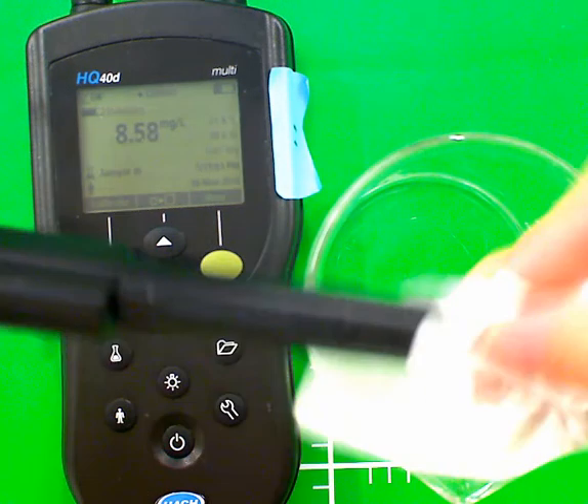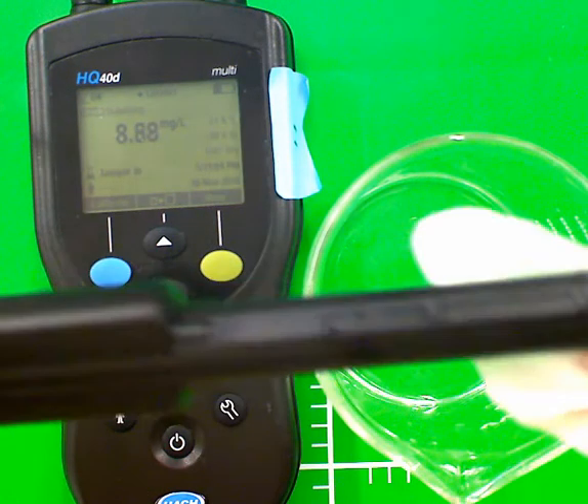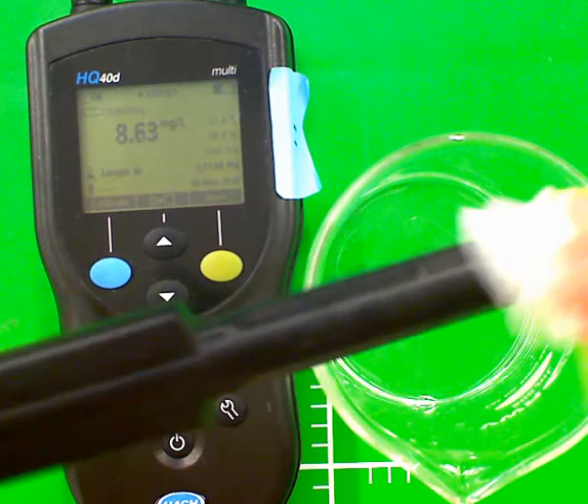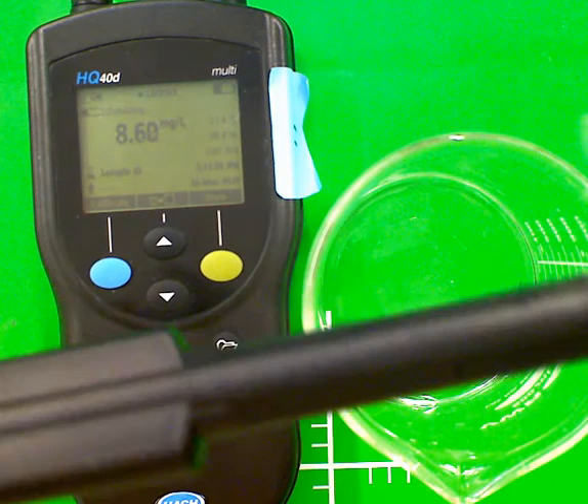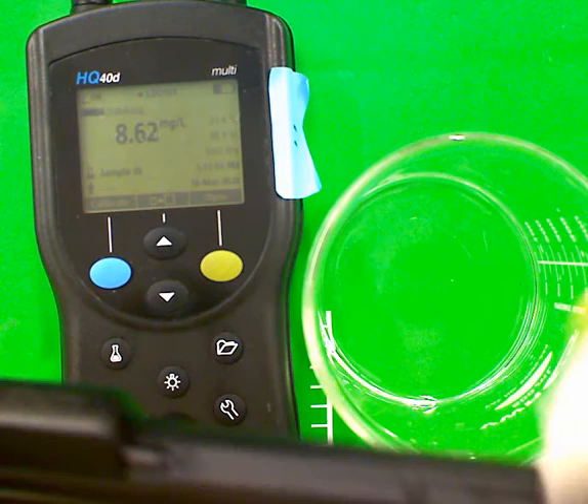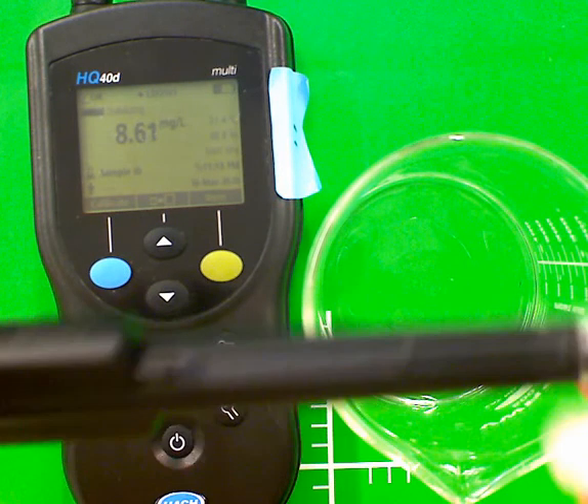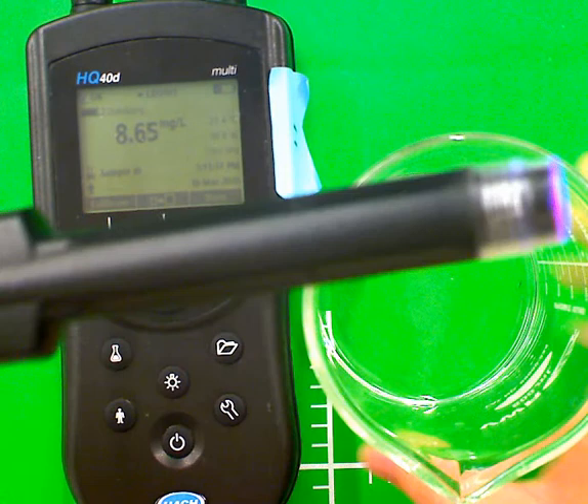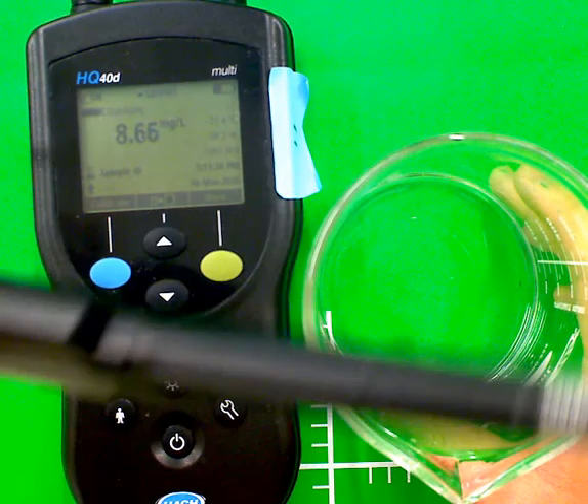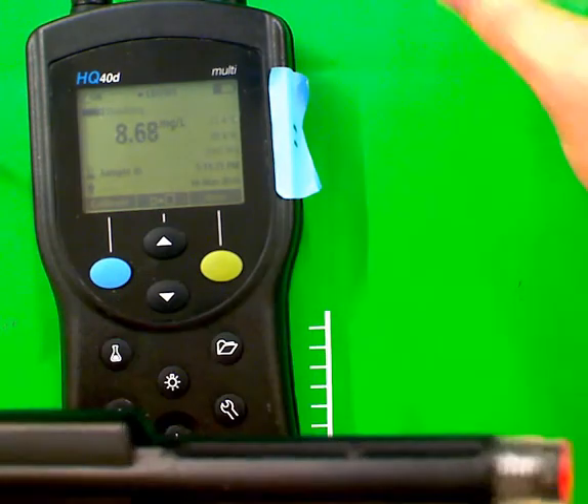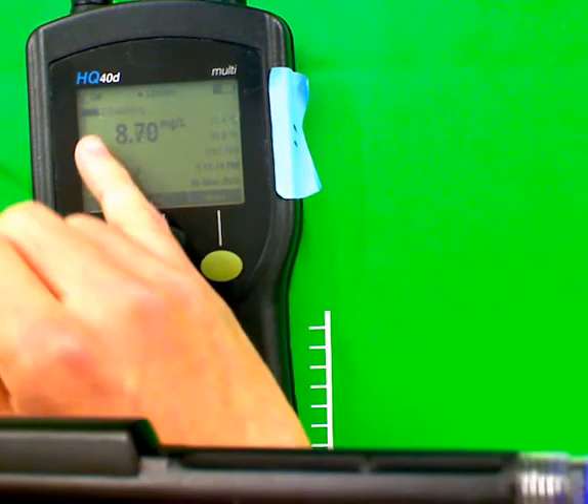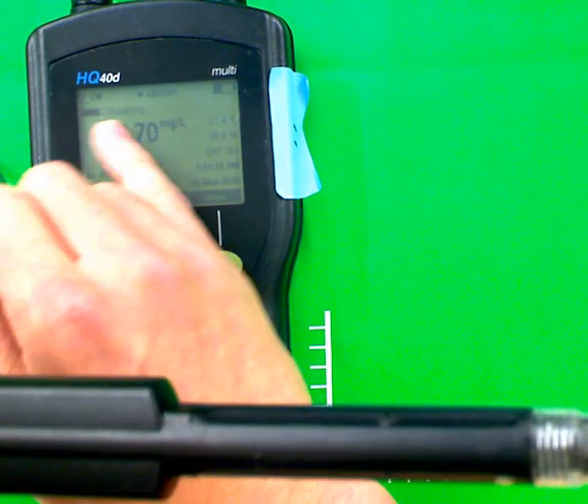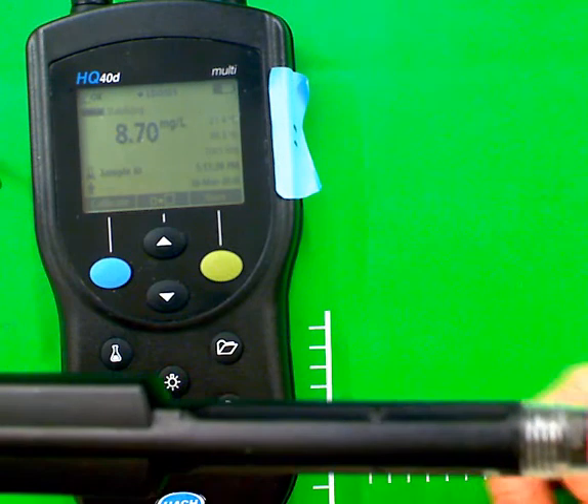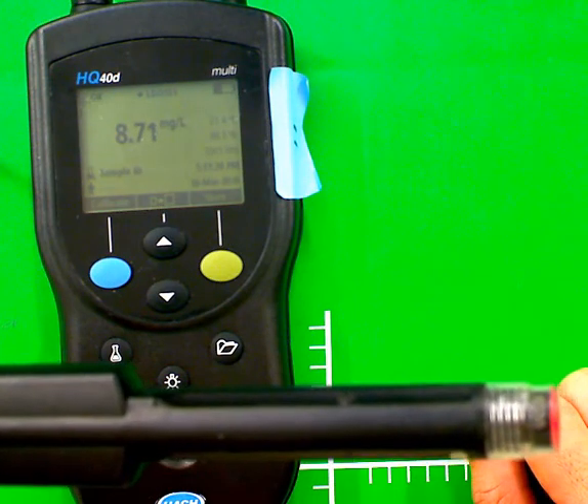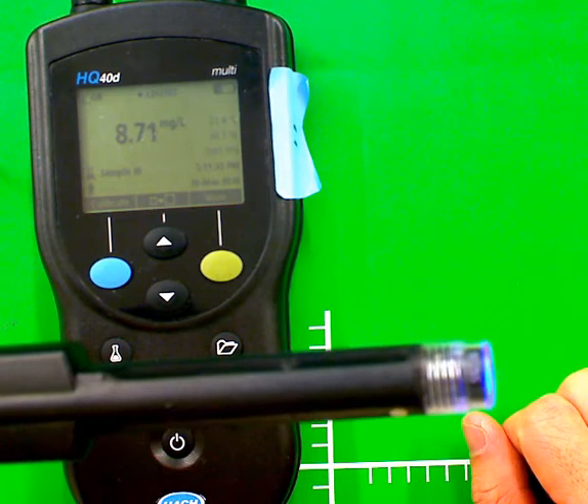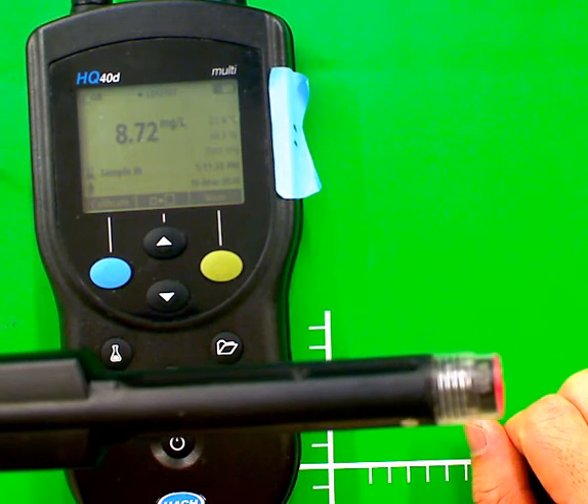Once we've rinsed the probe down, we wipe it down with this laboratory wipe, which is designed to not leave any lint whatsoever on the surface that it touches. Once this probe has been rinsed and dried, it is now ready to read a sample. You will now also notice that there is a bar here on the meter saying stabilizing and filling slowly. Once this bar disappears, that is how we know that the probe is stable and that the data that it is representing can in fact be recorded.